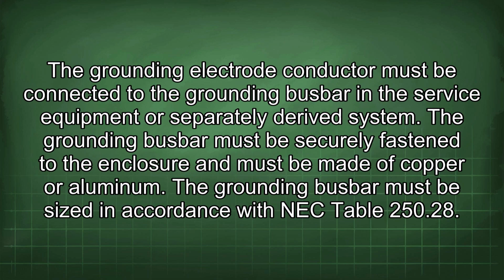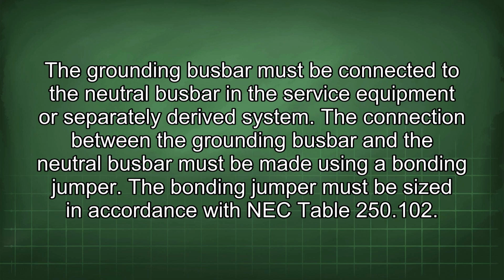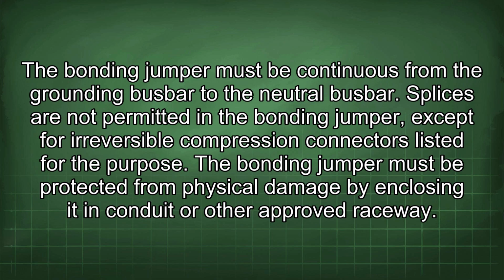The grounding electrode conductor must be connected to the grounding busbar in the service equipment or separately derived system. The grounding busbar must be securely fastened to the enclosure and must be made of copper or aluminum. The grounding busbar must be sized in accordance with NEC Table 250.28. The grounding busbar must be connected to the neutral busbar in the service equipment or separately derived system. The connection between the grounding busbar and the neutral busbar must be made using a bonding jumper. The bonding jumper must be sized in accordance with NEC Table 250.102. The bonding jumper must be continuous from the grounding busbar to the neutral busbar.